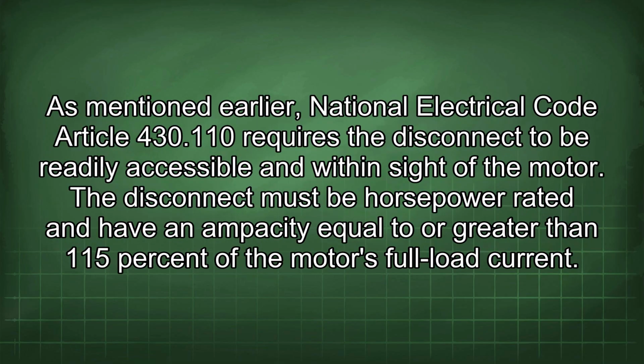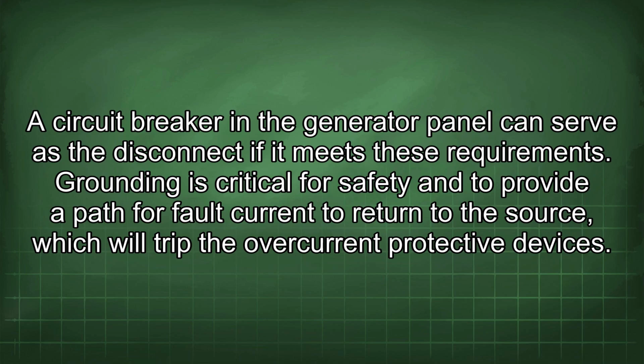As mentioned earlier, National Electrical Code Article 430.110 requires the disconnect to be readily accessible and within sight of the motor. The disconnect must be horsepower rated and have an ampacity equal to or greater than 115% of the motor's full load current. A circuit breaker in the generator panel can serve as the disconnect if it meets these requirements.